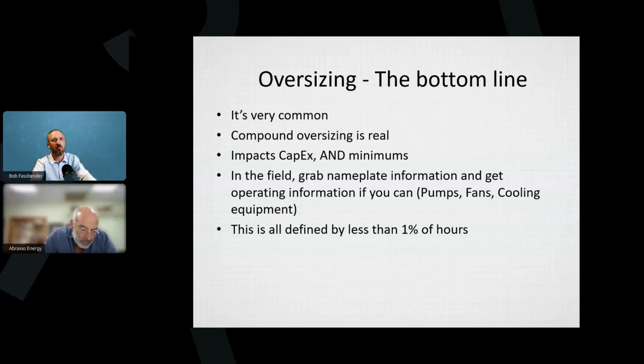Say we're sizing a pump for fan coil units, okay? There are 100 GPM apiece, and there's 100 of them. Some people will say that that's 10,000 GPM, but we know they're not all going to peak at the same time. Right. And so we want to account for that diversity across multiple items. You're going to oversize it, but that is part of the process, but don't keep oversizing it to be safe. And there are standards to follow.